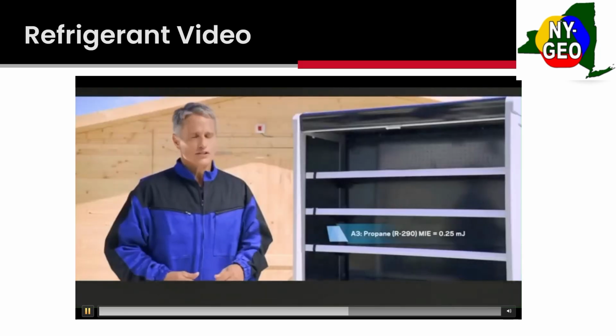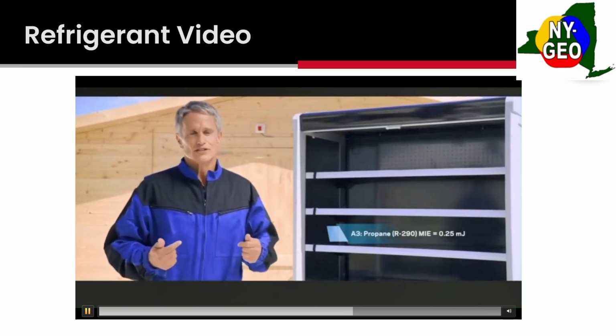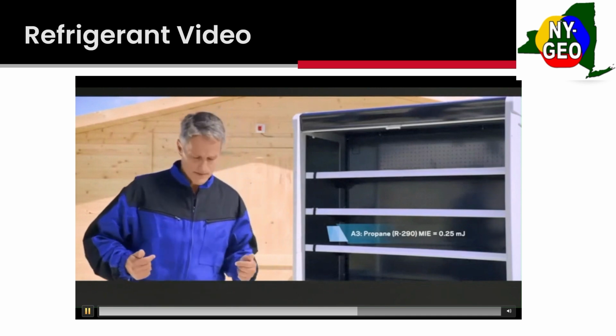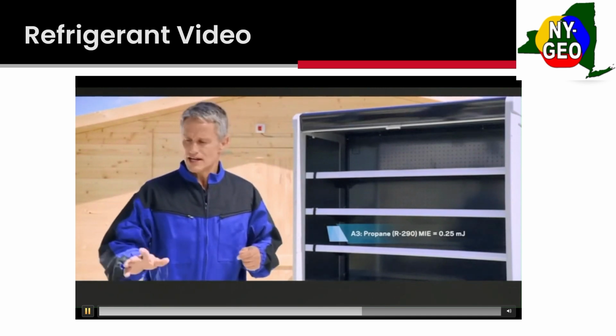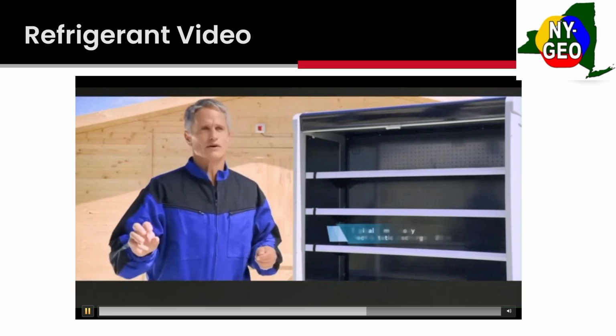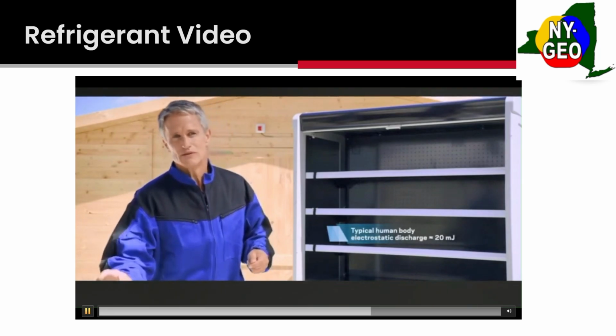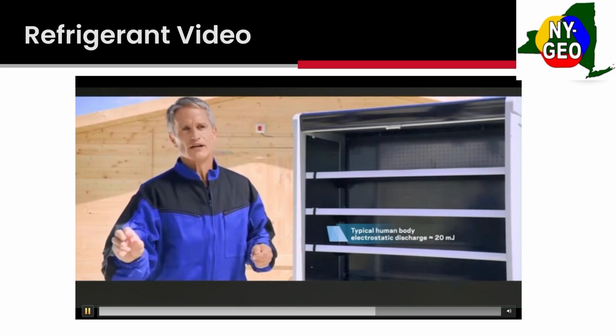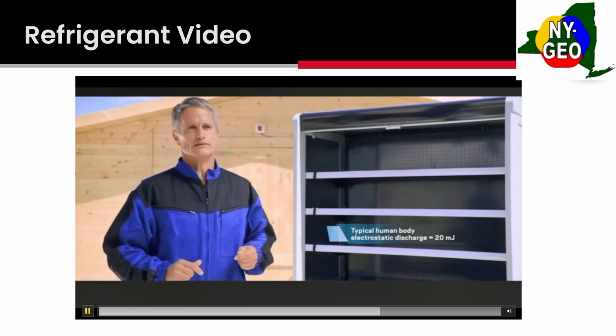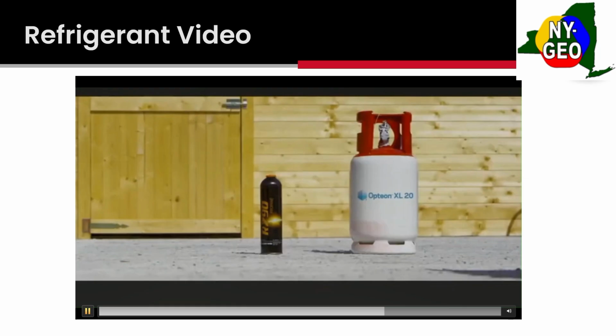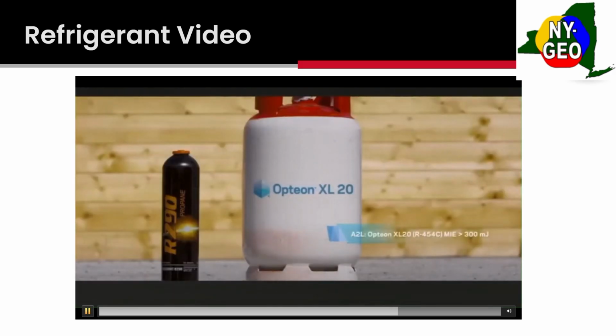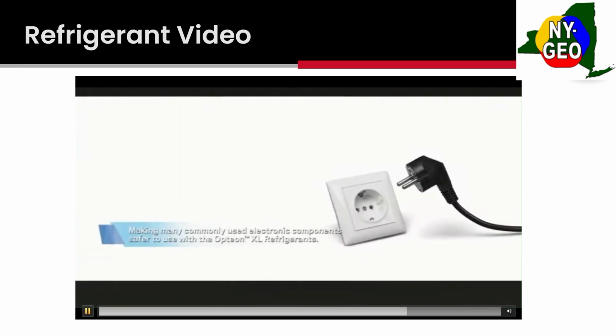To give you an idea of what millijoules are, say for example in the wintertime, I'm shuffling my feet on the carpet and I touch a door handle and shock myself. That value is actually 20 millijoules, or almost 100 times higher than the energy necessary to ignite propane. In comparison, A2L refrigerants have minimum ignition values 2,000 times higher than that of propane, meaning much higher energy sources are required in order to obtain ignition. This also means that many commonly used electronic components can be used safely with Opteon XL refrigerant.